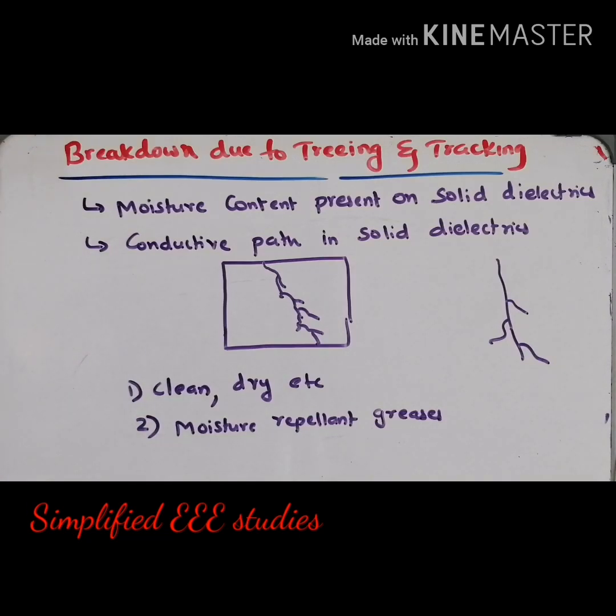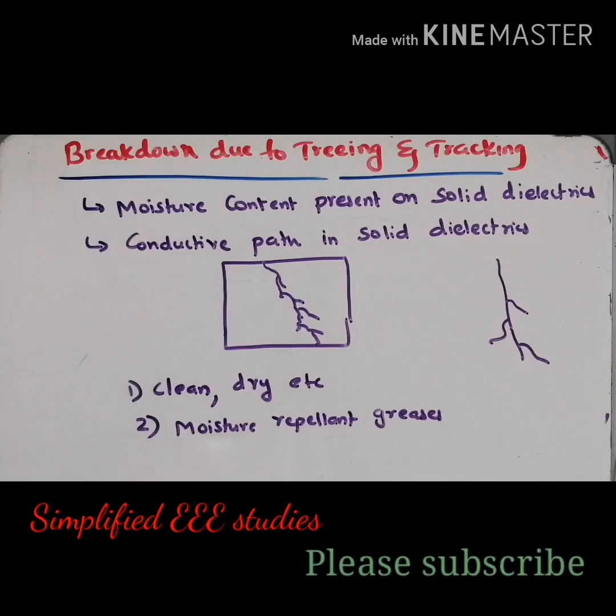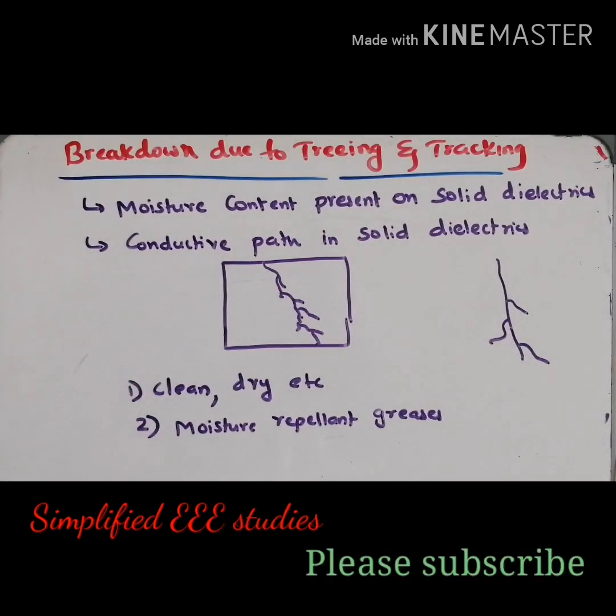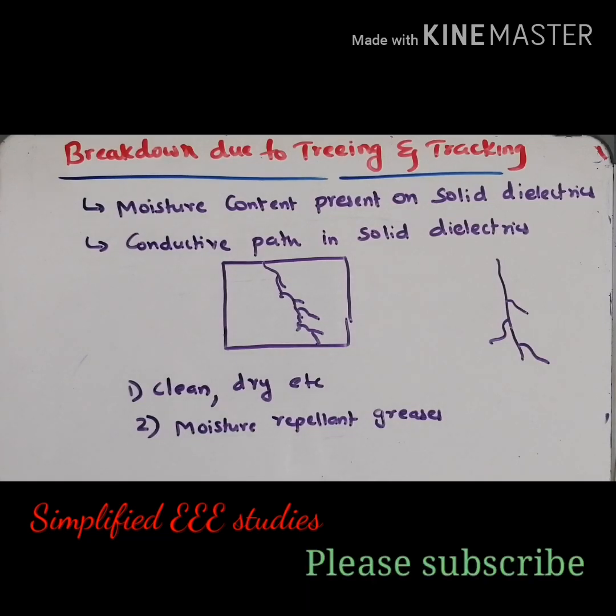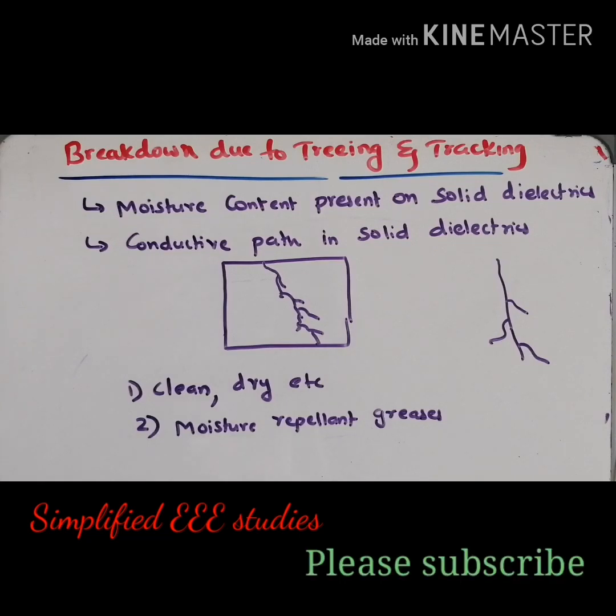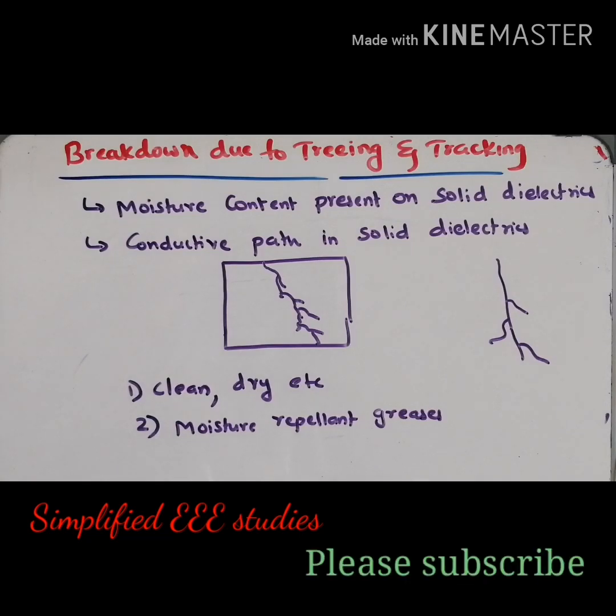To conclude the session: initially I explained the main reasons for the formation of treeing and tracking — mainly because of moisture content. Because of moisture content, slowly there will be formation of a conductive path inside the solid dielectric material. If a conductive path forms, the solid dielectric material is about to undergo breakdown, meaning its insulating property is getting damaged. To overcome treeing and tracking, keep the material clean and dry, and use moisture repellent greases to get rid of moisture content.